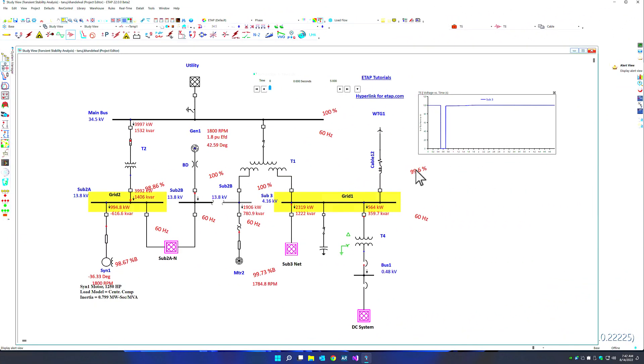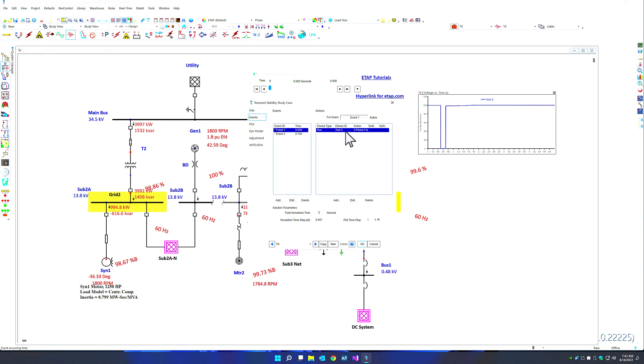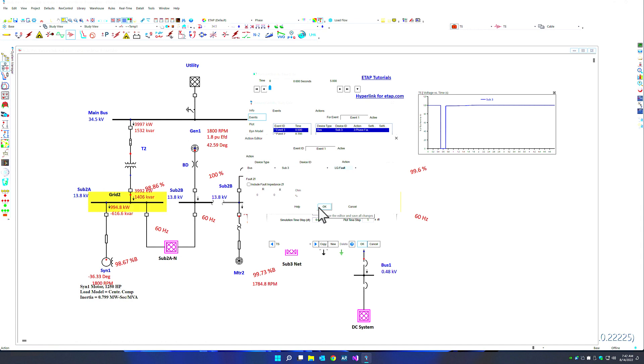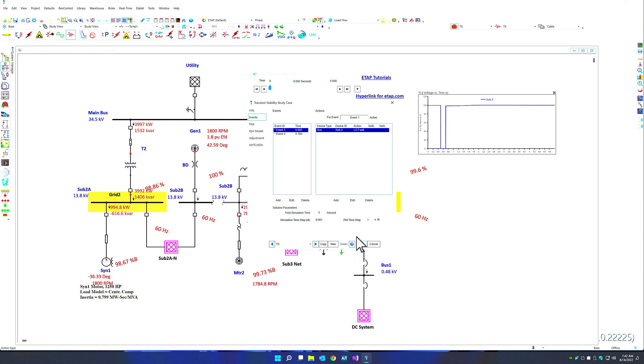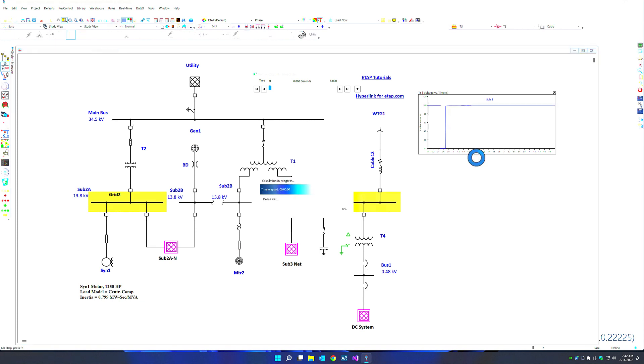For example, in transient stability, we can apply a three-phase fault on sub-3 bus, and we can see the voltage goes to 0%. We can quickly go inside the study case, change this action to line-to-ground fault, and we can also include an additional fault impedance and click OK and rerun the simulation.